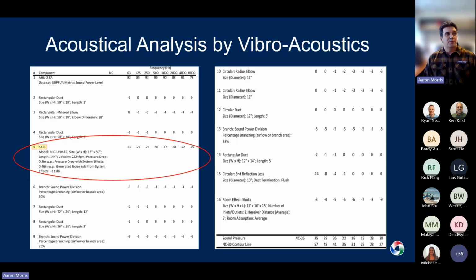So if we know our sound power level for our equipment and the requirement for the space, and we know our duct path, then we can send that information to Vibro-Acoustics, who can help us with an acoustical analysis that'll look something like this. Now we can start off with a baseline analysis just to show, with the top line showing the rooftop unit sound power levels, and then the distance it travels through the ductwork, different fittings, different branches that it's going to travel through before it gets to the classroom. We can calculate insertion loss values and show where we would be if we do not add sound treatment. And in this case, we were going to be well above the target of the NC30 contour line.